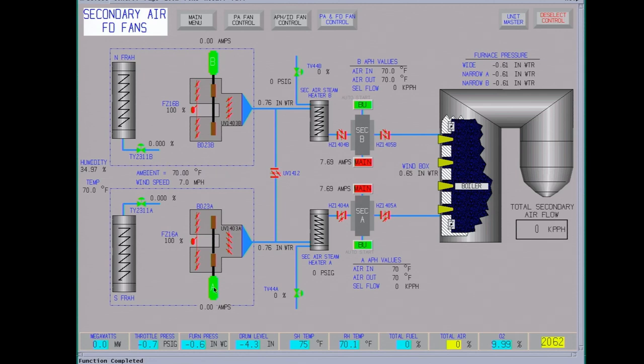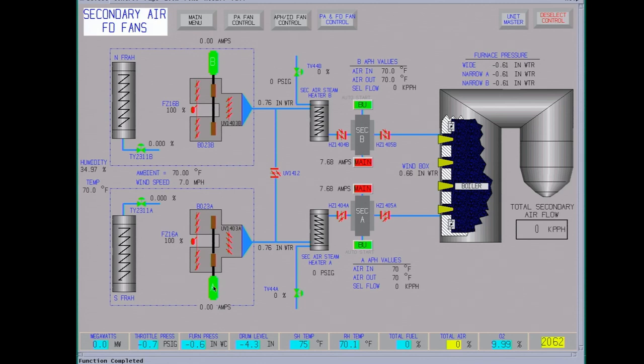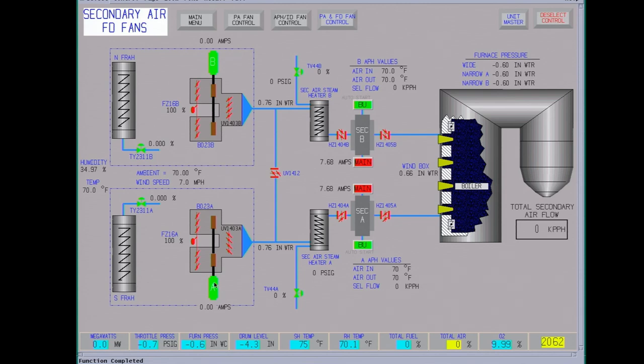Once again, you need to call out that you're starting the fan, let all personnel know. You need to have somebody out there just to verify that it started okay. Now we also raise the plant voltage up. These run 7,200 volts. As you start more motors, the plant line voltage will drop. So we change the taps on the auxiliary transformer and try and maintain a little over 7,200 volts. As your voltage drops down, it takes more starting current to start them. Too high voltage is hard on the insulation, the windings. So usually we try and maintain right around 7,200 volts. So we use the tap changer on the transformer and maintain around 7,200 volts on the motors.